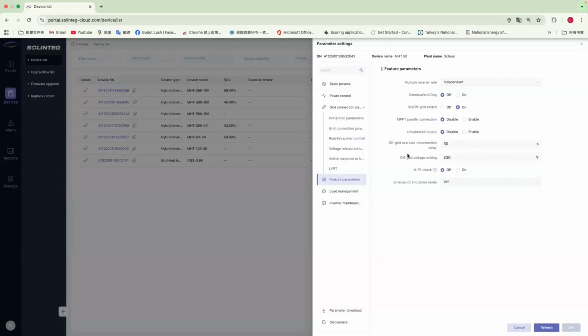For example, if we are in the off-grid situation and the power of the load we have is higher than the capability of the inverter, in this case, when the inverter detects that the power from the load is too high, it will enter into a waiting status and set this delay time so that you can receive the alarm and then check or turn off some of the off-grid load. And from here, we can set the off-grid voltage setting. And here is for us to set the NPE check.